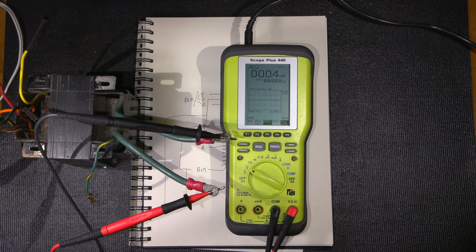So what I'm going to do now is turn on that supply. There's AC on that winding right now, and the Variac is turned down really low, and I don't even have a glow on the bulbs yet. So I'll turn this up, and they're just ever so slightly glowing, and that's at max right there. So if I click the dim bulbs out of line, there it is, 5.8 volts. So you can comfortably say that that is a 5 volt winding.